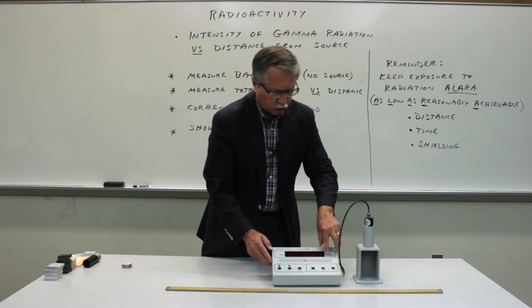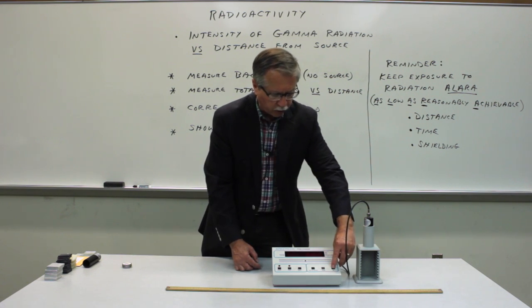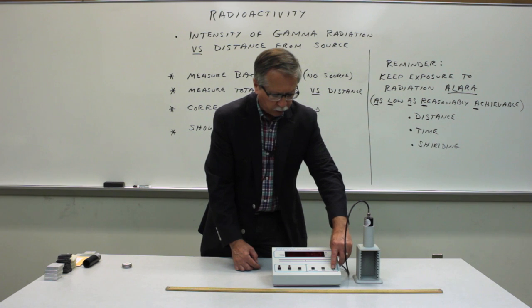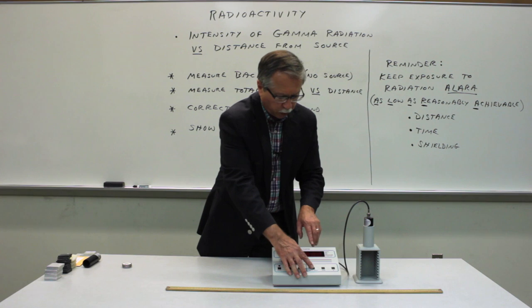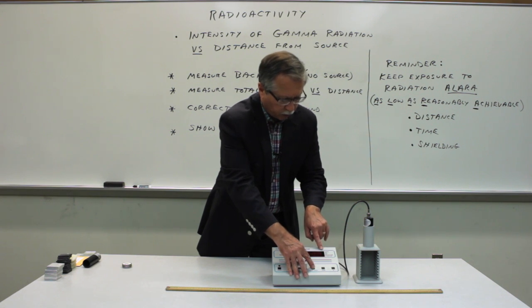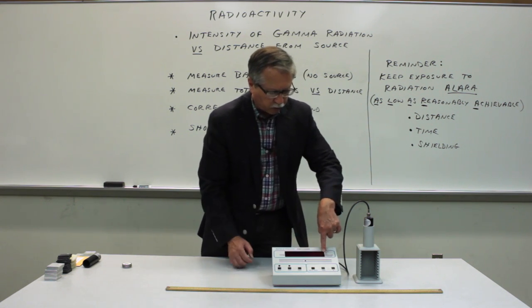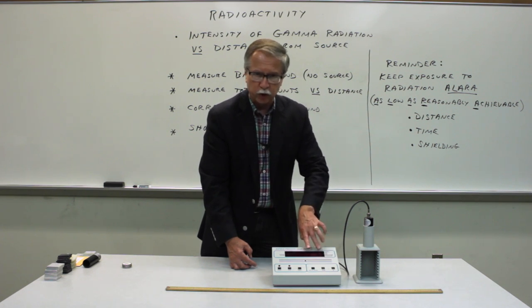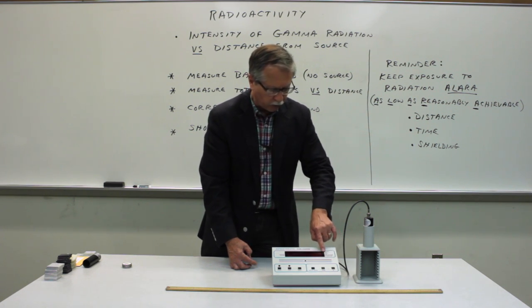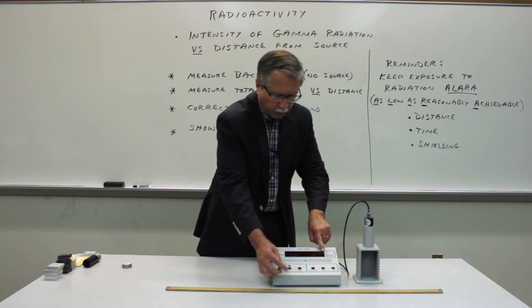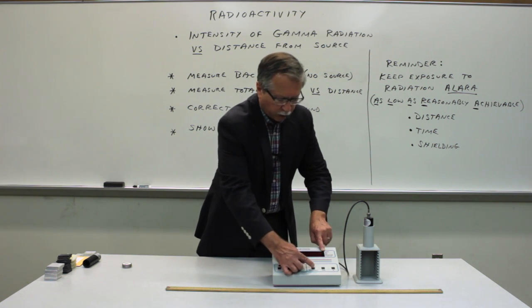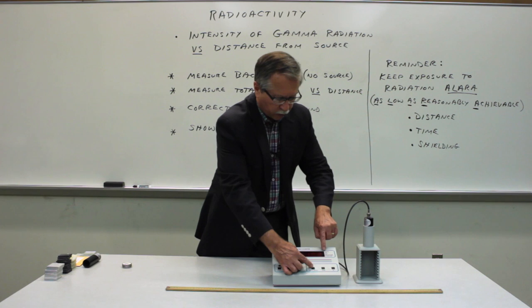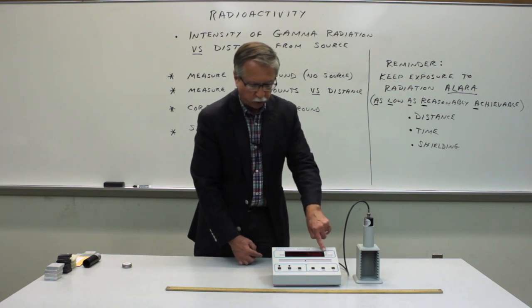I'm going to set this to 900 volts using the up button until we reach 900 volts. Then press display select again and set the time interval to 60 seconds or 100 seconds, or whatever a convenient time interval will be. Then press the select function again until we get back to the count function.